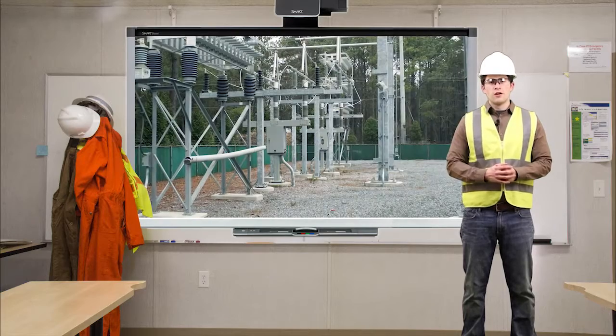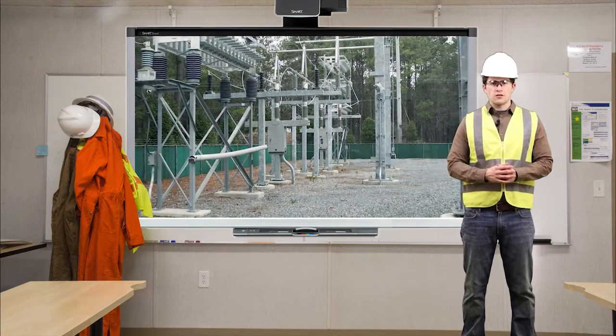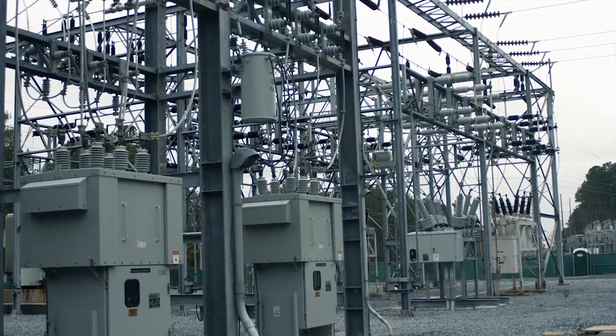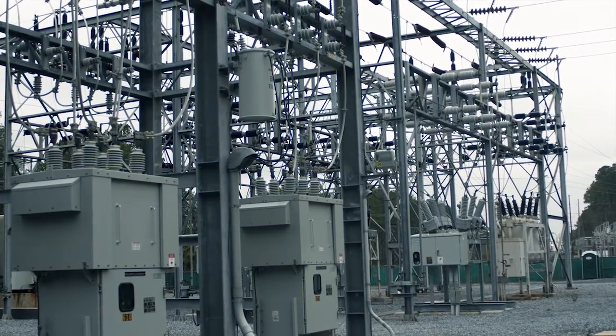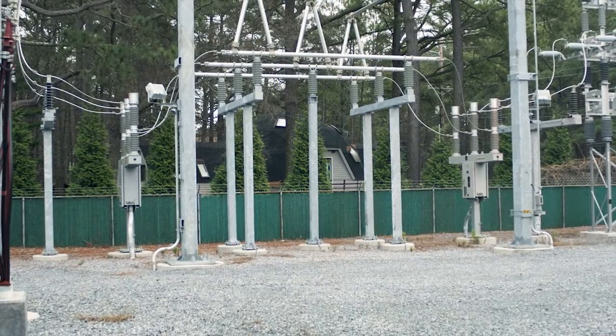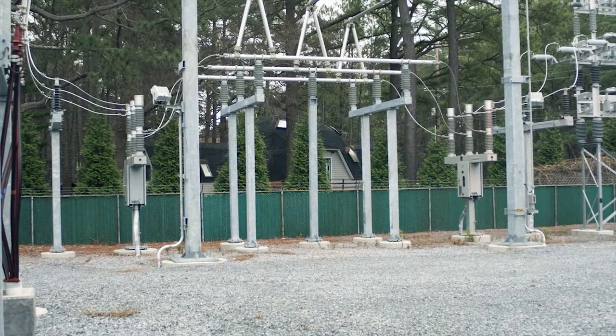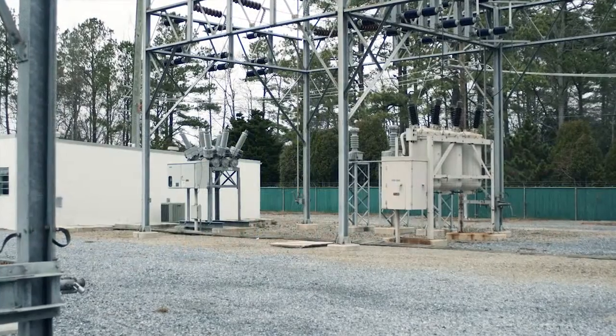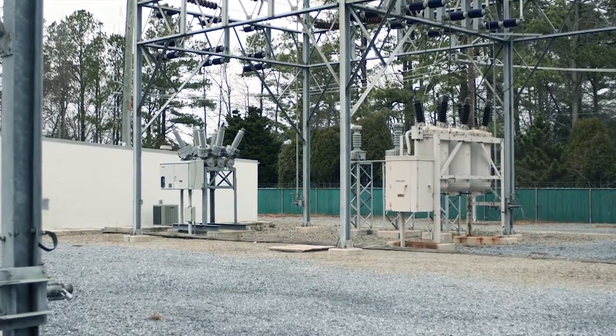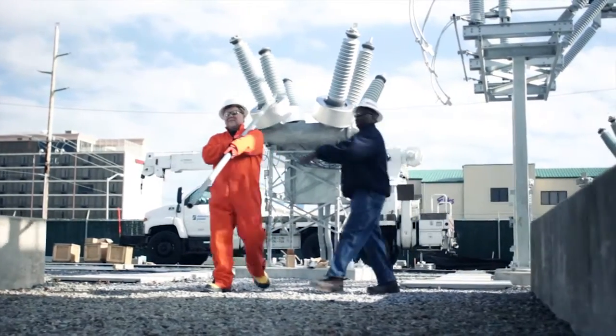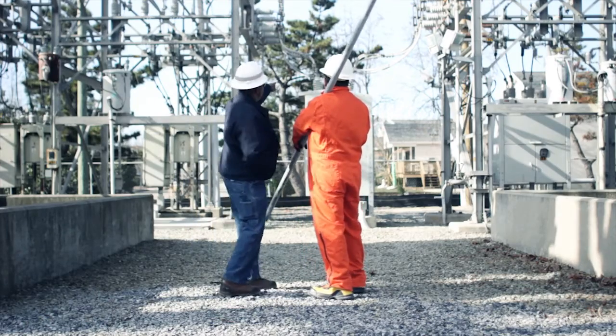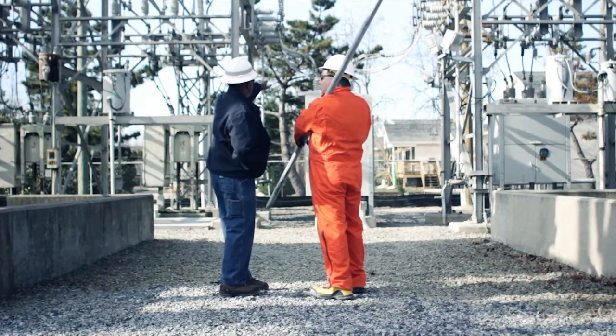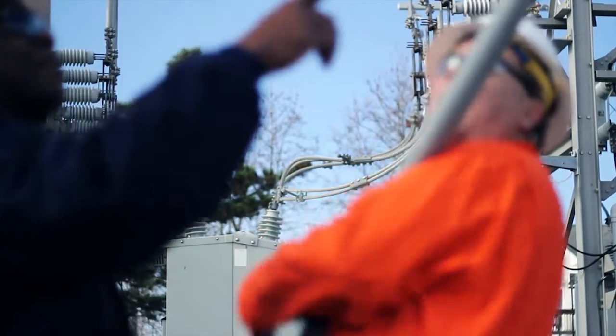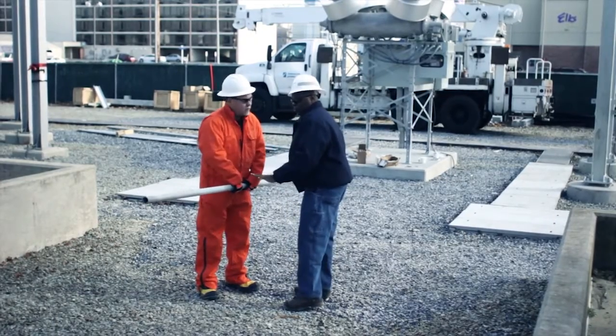As mentioned earlier, most but not all uninsulated conductors are elevated. Be aware of the low conductors and station service transformers. Low conductors also pose clearance issues to larger vehicles like mobile cranes, dump trucks, and concrete trucks. No material or tools of any description shall be carried on the shoulder. All long materials such as lumber shall be carried in a horizontal position either at or below waist level.